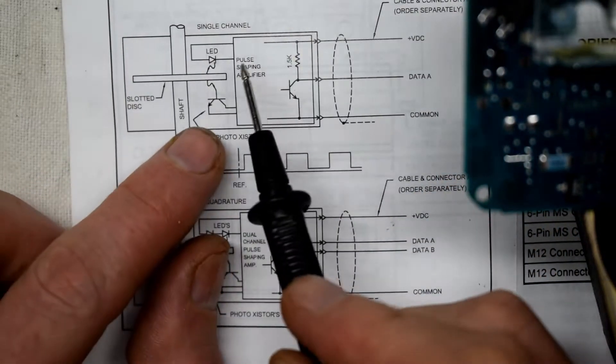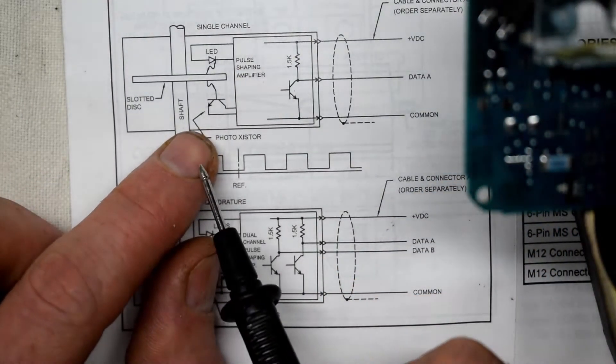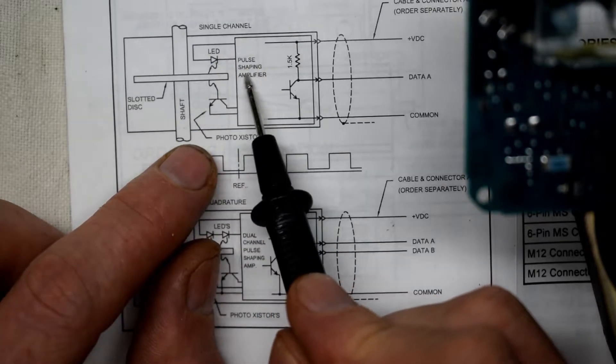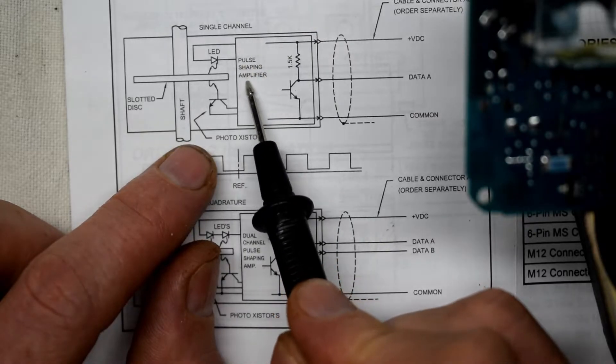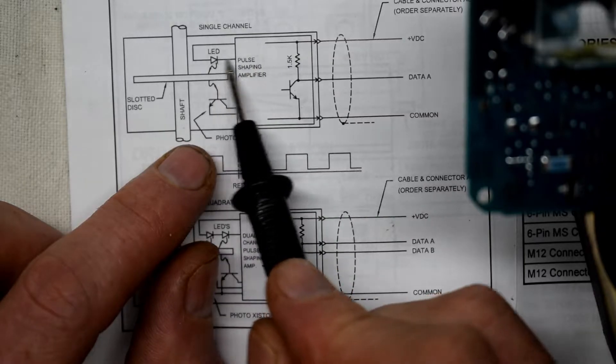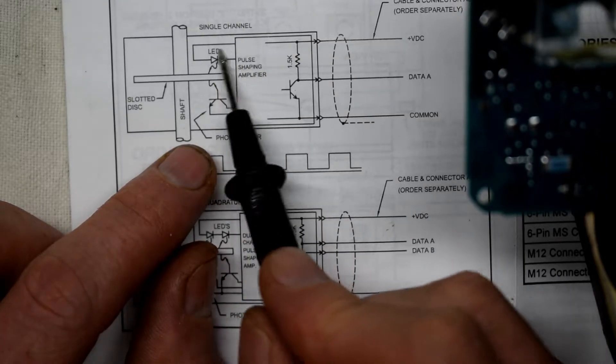And normally what blows is this LED right here. And then there's a pulse shaping amplifier. There's an N-channel MOSFET that blows in series with this LED. And you have to replace these two.